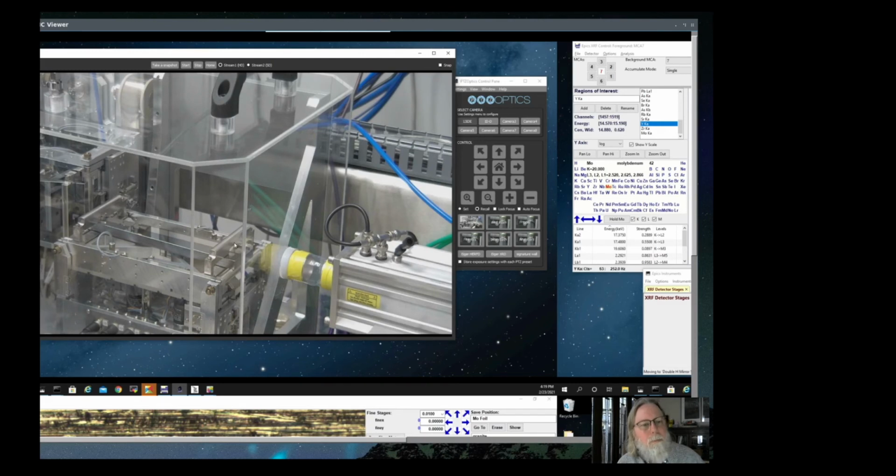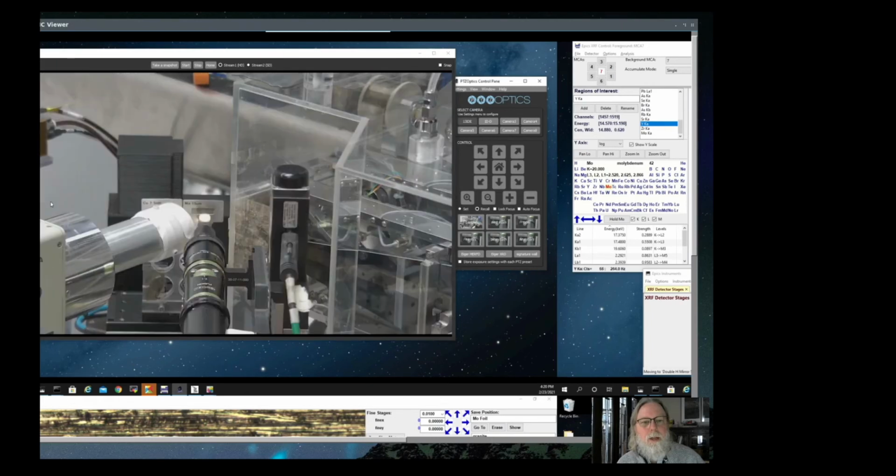The X-ray beam goes through this little slot here. We push down on those bars to try to make an ellipse. The X-ray beam goes through that, and the ellipse focuses the beam from the spot that is the source, 50 meters upstream, to your sample. And then there's another mirror that focuses in the vertical here.